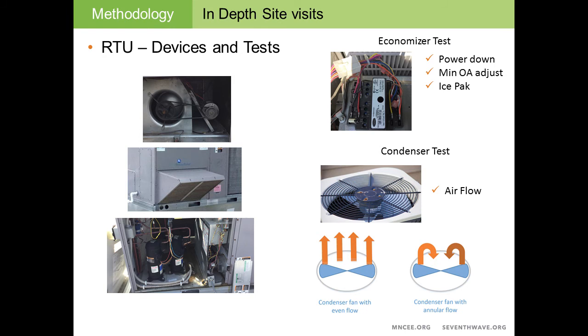More subjective tests that we had done are a condenser airflow test. We passed our hands across the condenser fans to see if airflow is even across the face of the condenser fans. And this is a good indicator of whether the condenser coils themselves are plugged or not. In the event that the airflow is plugged, the condenser fans will set up more of an annular flow, where the air will exit the outside of the fan and then enter into the center of the fan, because the fan tries to achieve airflow even if the condenser is plugged. So these are some examples of the tests that we did.